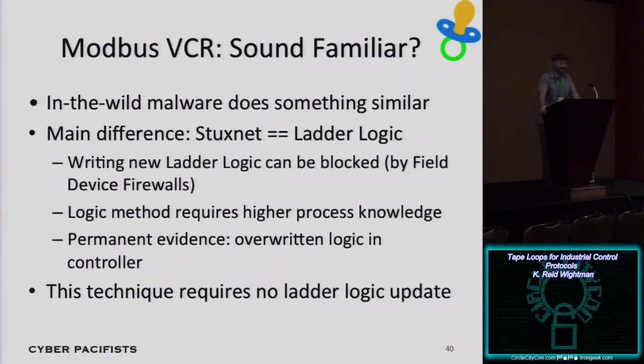There's an in-the-wild piece of malware, Stuxnet, that does a similar thing against a control system protocol—the Siemens S7 controllers. The big difference is that Stuxnet actually modified ladder logic in the S7 controller to do its attack, and you can block that ability to upload new ladder logic with one of these firewall things. Also, actually doing that ladder logic attack requires that you pretty much know everything about the process beforehand—you have to know what the ladder logic in the controller looks like so you know which input states are important to spoof.